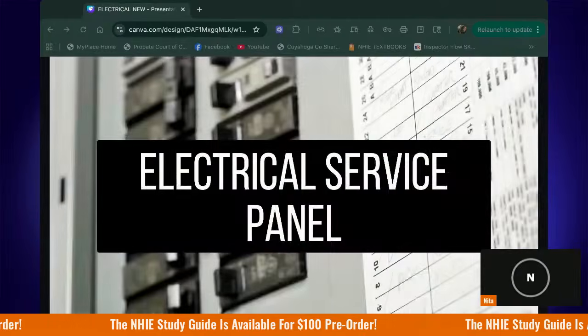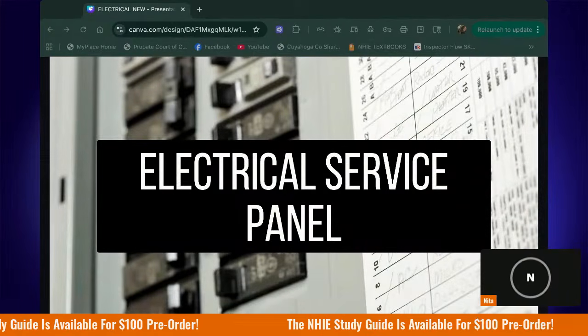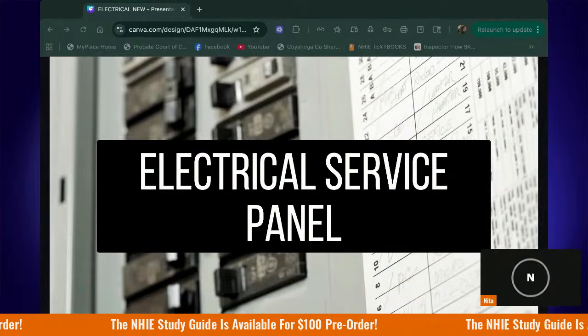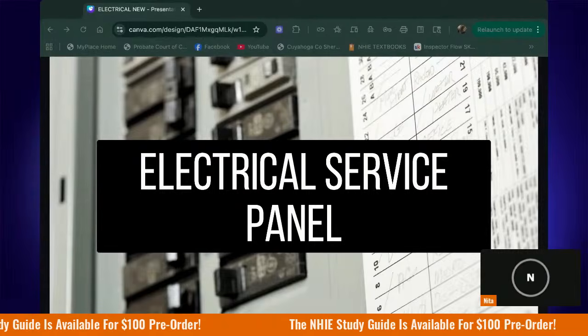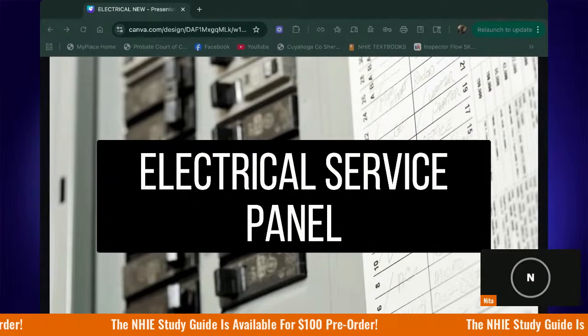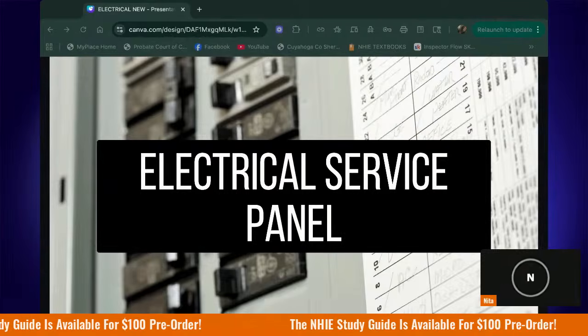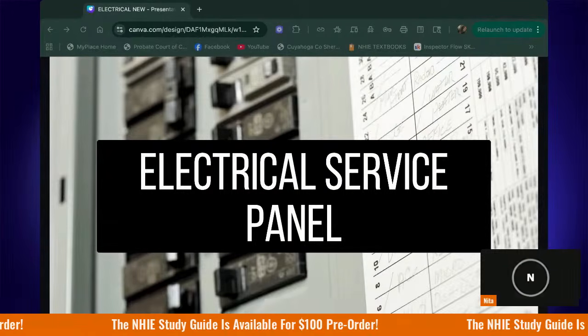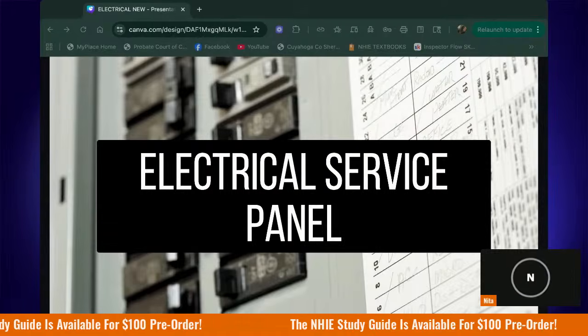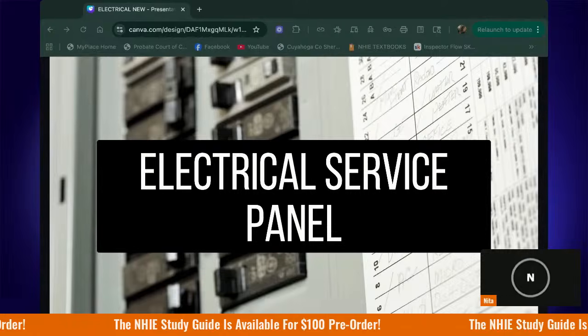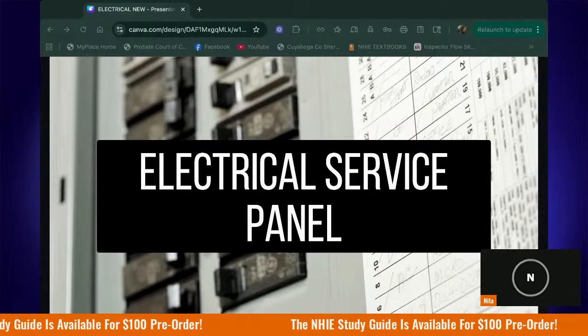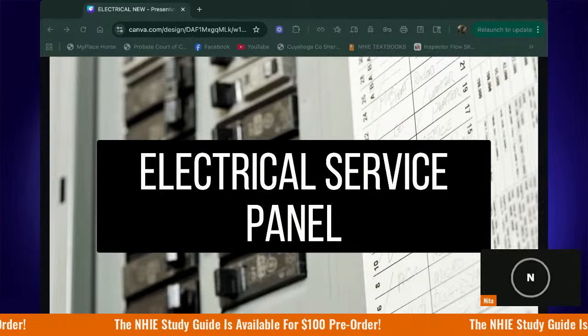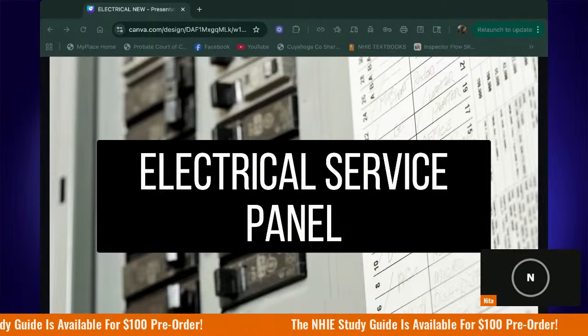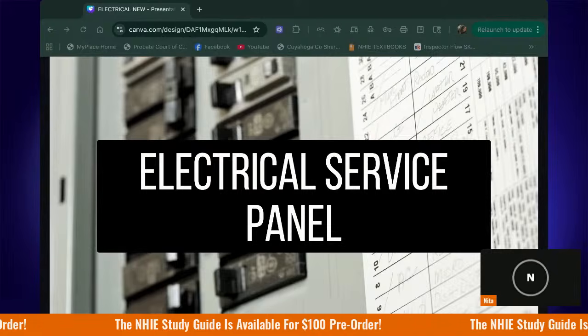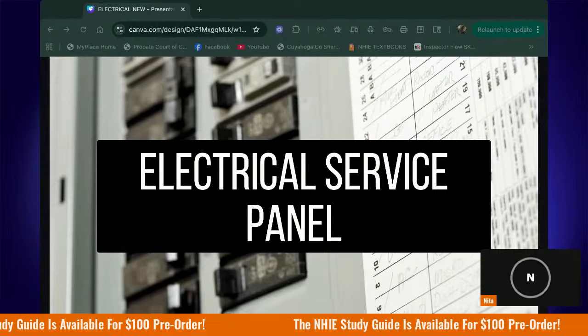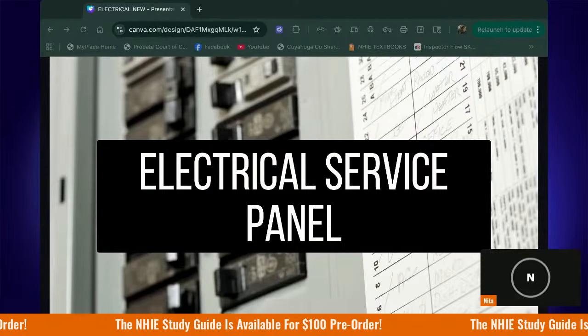Okay, let's get into the panel now. So the panel is basically, again, like the control center. It's the central hub for the whole electrical system. This is where the incoming power, like we just learned, comes from and is distributed through the house. And it's also where some of the safety features are to protect us from fault currents and things like that. So we already talked about service equipment, referring to the components that serve as a disconnect, and that allow electrical supply to be distributed throughout the house. So you will sometimes hear it called main disconnect, main breaker. These are all the same things.